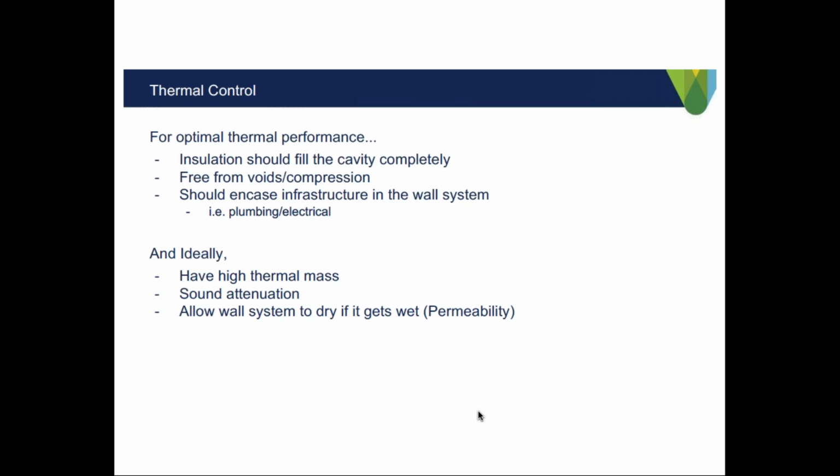So when I say that, I mean, if it's cold on the outside of the building, the air is more dense as it touches that exterior surface. It falls to the bottom of the cavity. As that air works towards the inside, it actually warms back up and creates a loop, and that air rises. And so all the time, air is rising and falling in a wall cavity, which degrades the overall R value of that insulation. So you may be paying for an R19, and you may be getting an R5. So, install quality is a huge issue and something that is definitely more difficult in a retrofit scenario.